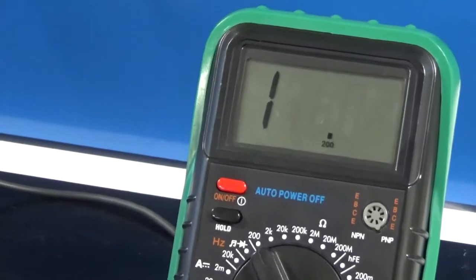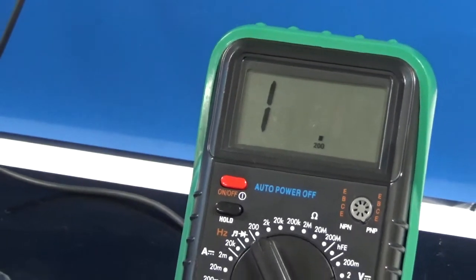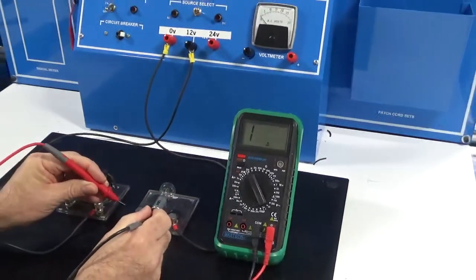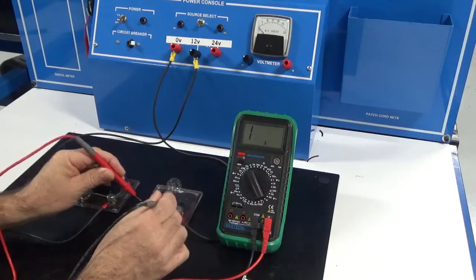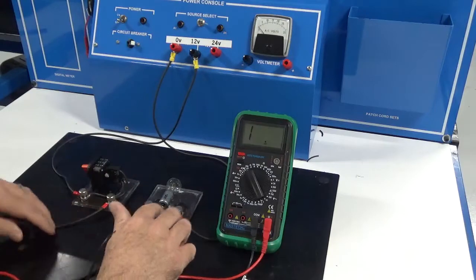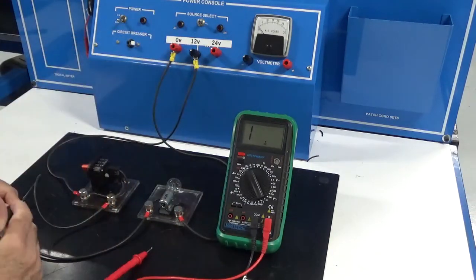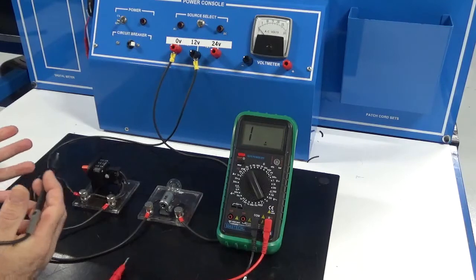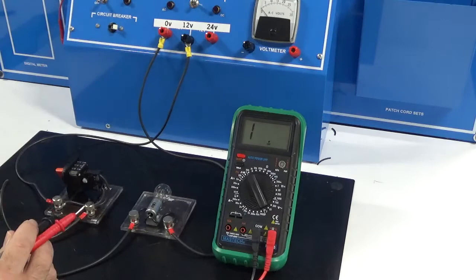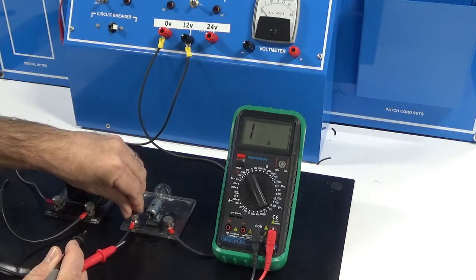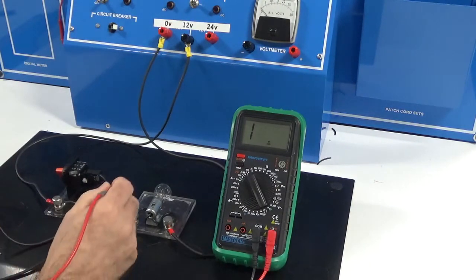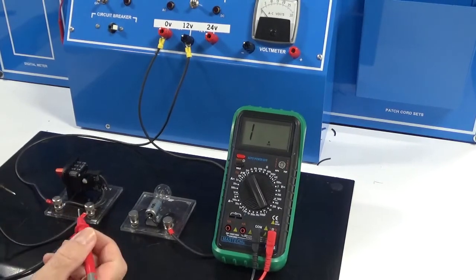Now, there's one thing you need to understand when you make a resistance measurement. I've got a complete circuit here. So if I wanted to measure the resistance across this lamp, if I didn't disconnect anything and just touched the lamp, I'm not only reading the resistance across the lamp, but if you follow my circuit around, I'm actually going to be reading resistance through the power supply as well, and it's going to give me an inaccurate measurement. So when I'm measuring the resistance across a component, I have to isolate that component. To do that, I don't have to remove both sides. I just need to remove one side to remove that alternate path for the resistance measurement.